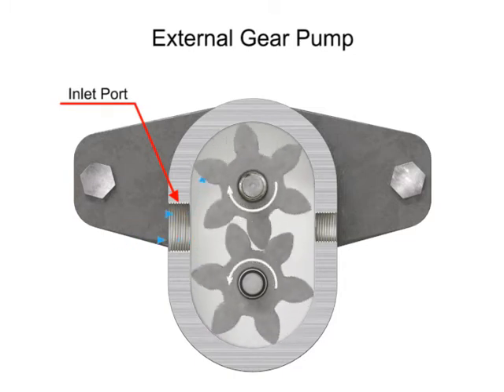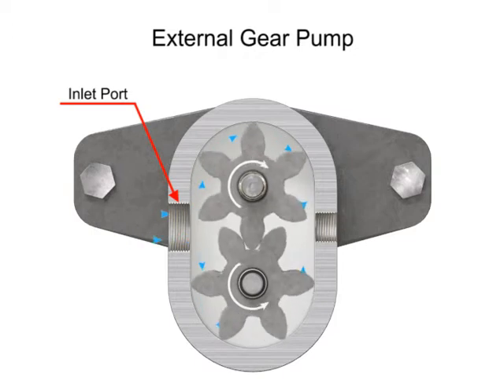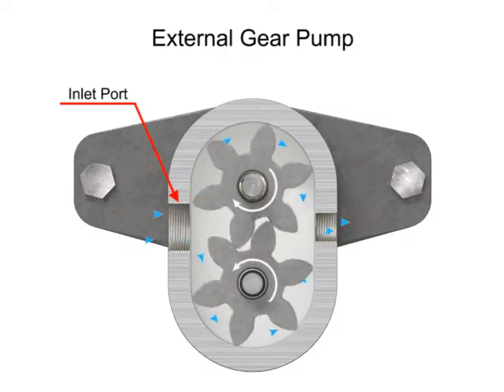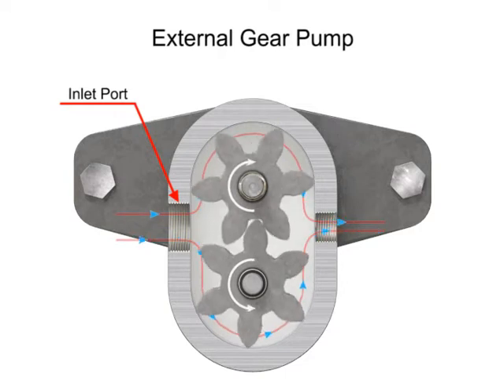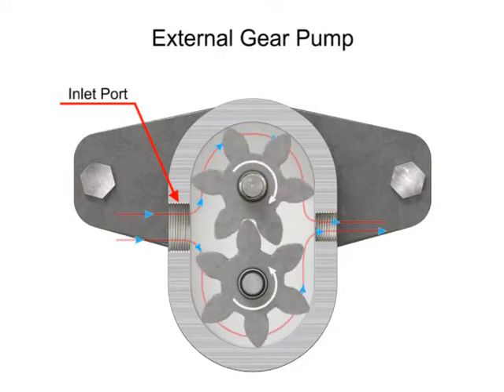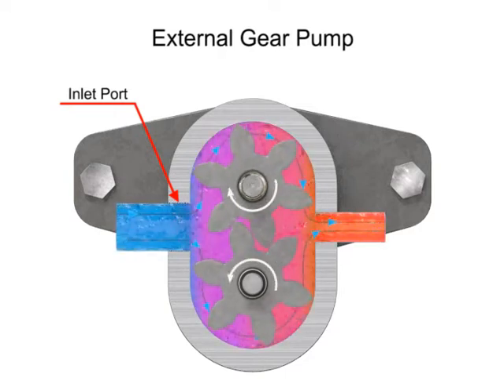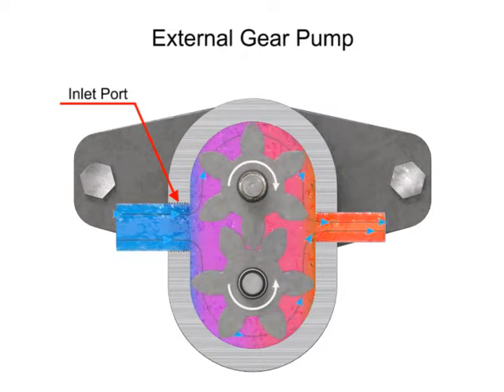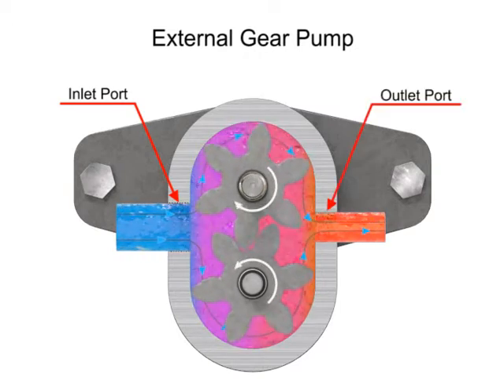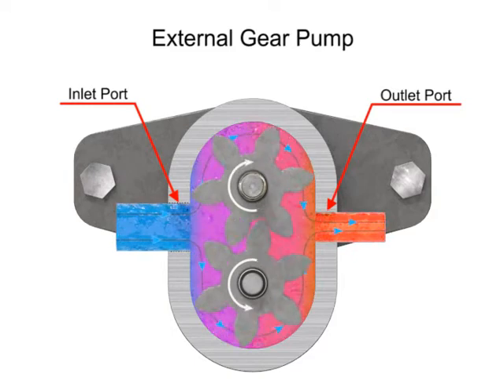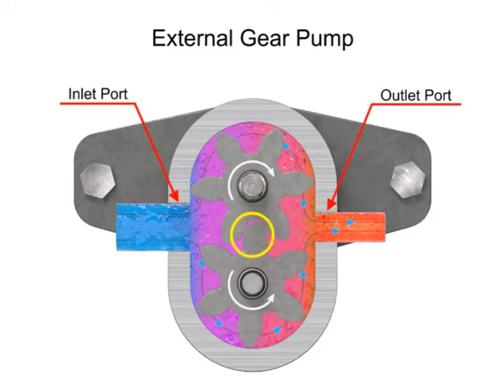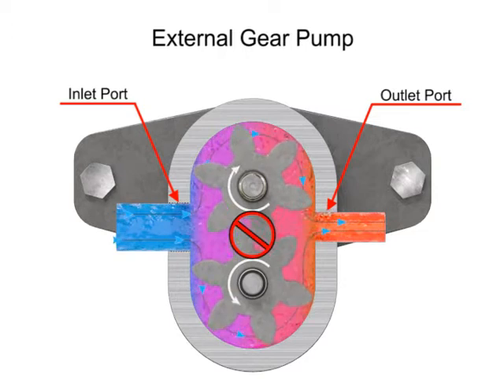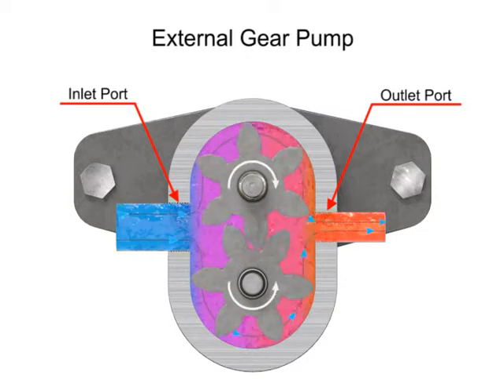Fluid flows into the cavities and is trapped by the gear teeth. As the gears rotate, a flow path is created around the outside of each one. Fluid trapped in the slots between teeth is carried around and discharged into the cavity with the outlet port. Meshing of the teeth in the center of the pump seals the outlet port from the inlet port, and no fluid passes between the gears.